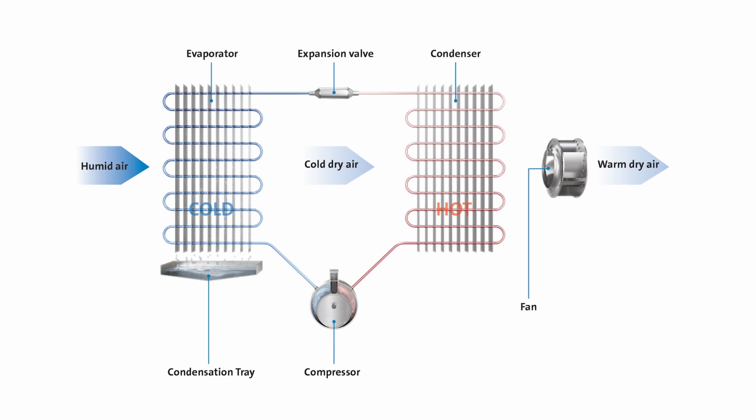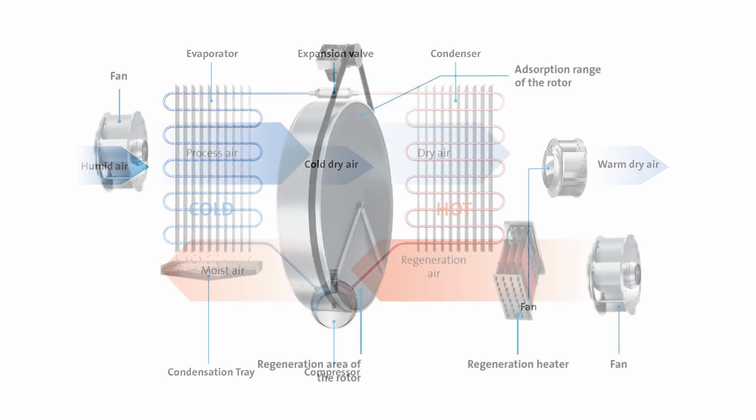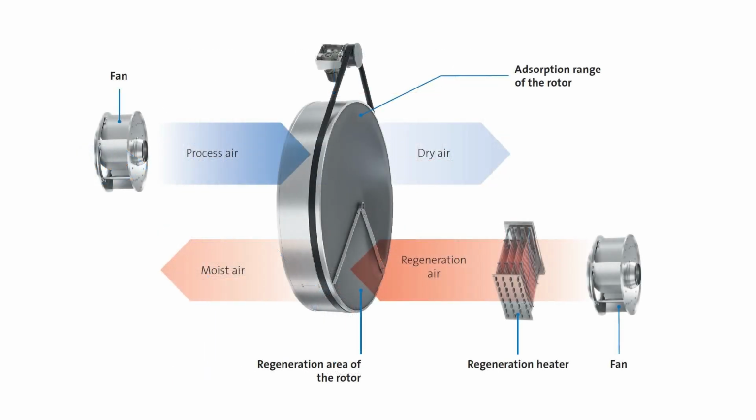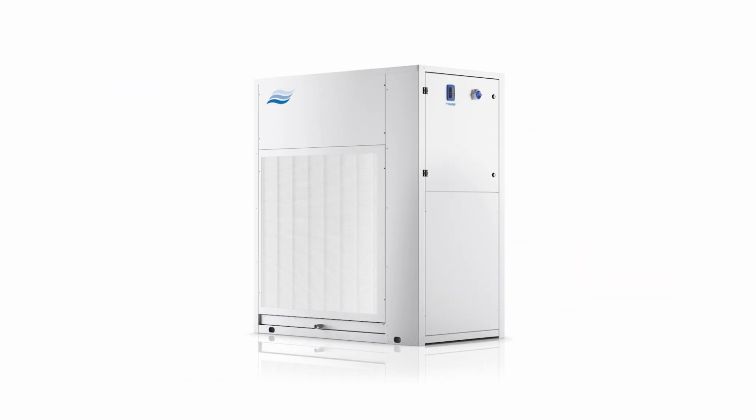When temperatures drop to around 15 degrees C or less, condensing dehumidifiers just aren't very effective. So desiccant dehumidifiers become the preferred option. Now, they need more energy to operate and can be more complicated to install, but as they remove water from the air by simply absorbing it like a sponge, they work well in either warm or cold areas. Okay, so the condensing type is good for warm areas and desiccant for cold? Yeah, but it's not quite so simple.